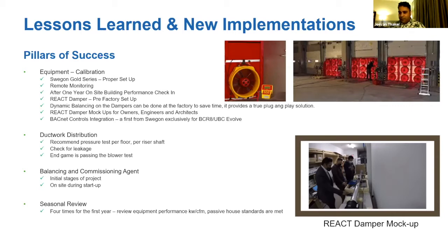We couldn't get the project balanced. And I think a lot of construction people are catching up to the tolerances they need to meet, specifically with ductwork. For example, if you're dealing with a hospital, 80,000 CFM of air handling, and you have a little bit of ductwork leakage, you're probably going to be okay, right? You may have 10%, so you might lose 8,000 CFM. Now you're down to 72,000 CFM on an 80,000 CFM unit. Still not good, but probably okay, right?